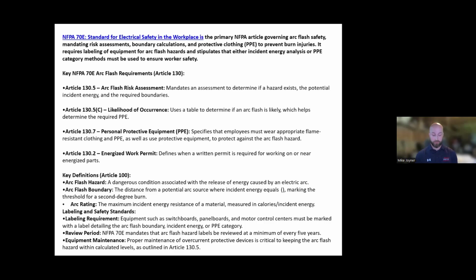Nope, that was perfect. I was about to dive into that because you don't want a 20 amp breaker that could shut down not just a panel, but a whole entire piece of switchgear. Nuisance tripping could shut down a whole entire building, which has happened multiple times.